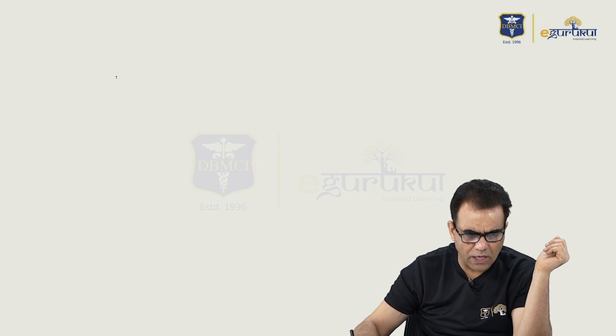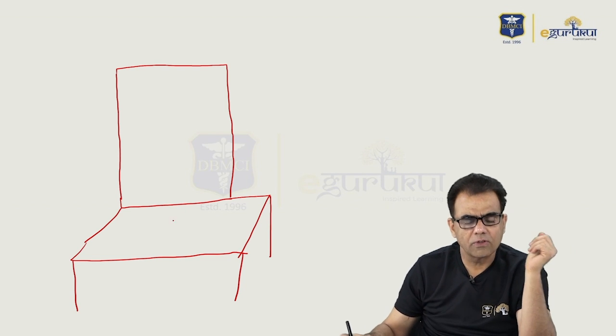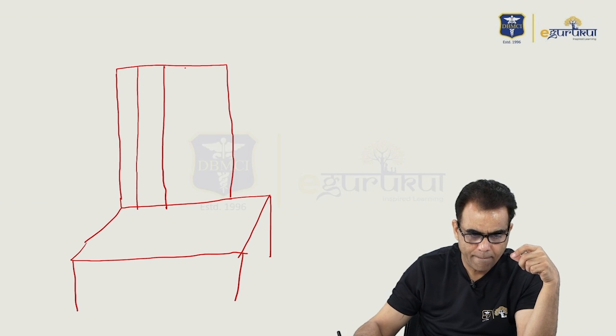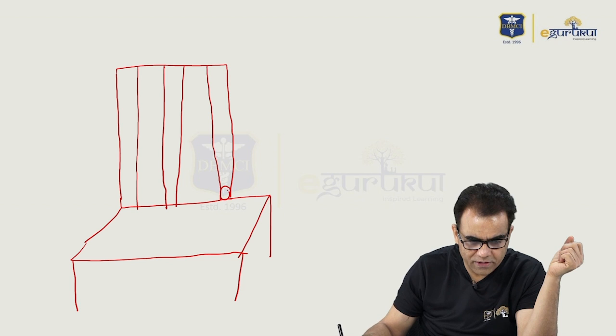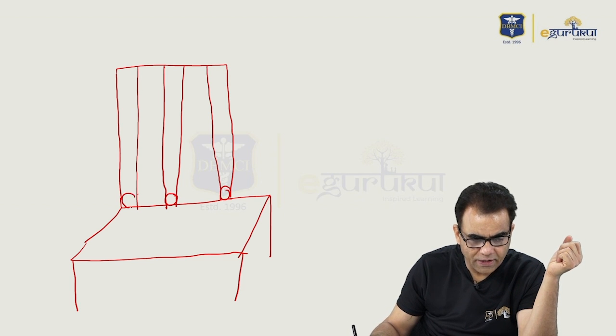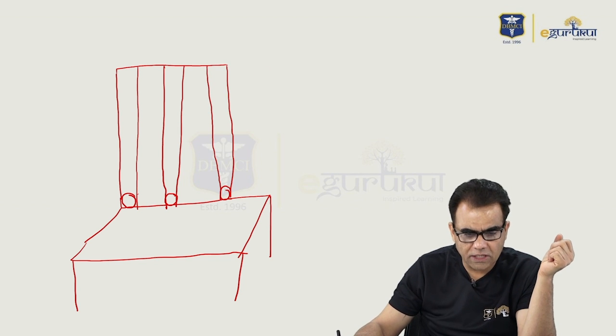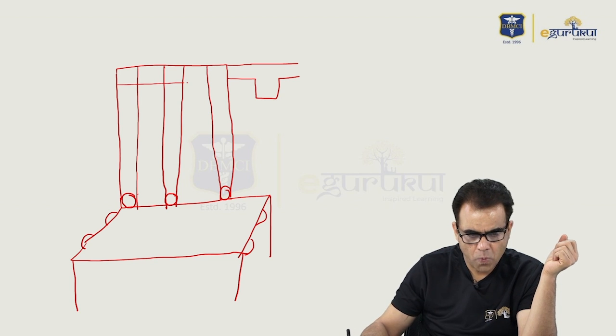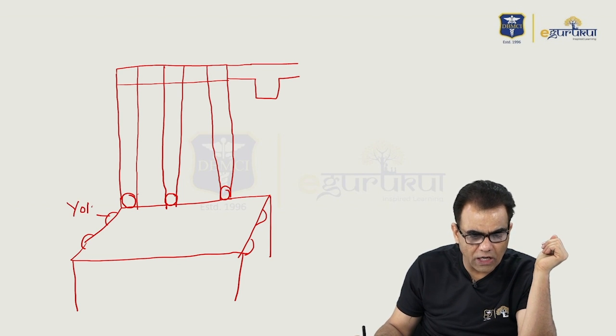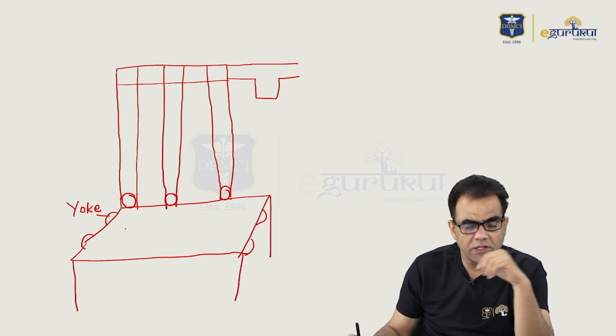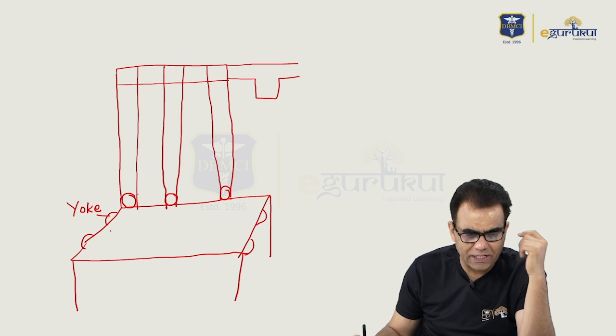I am drawing the outline of the anesthesia machine so that you can understand it better. This is just an outline of the anesthesia machine — do not go by my drawing, it is really not perfect, everything is not straight. Cylinders or central supply will be positioned and attached here, and the portion of the anesthesia machine where cylinders or central supply are fitted is called the yoke.